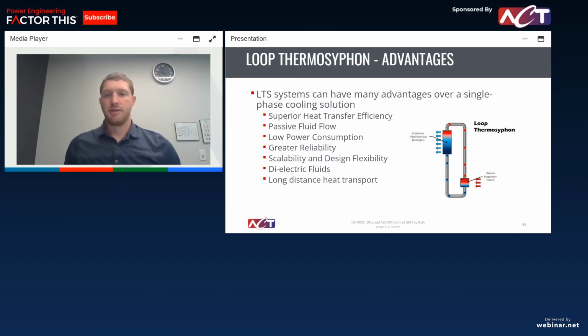So looking at some of the advantages we have over a single phase cooling solution, as we talked about, in general, two phase, you have superior heat transfer efficiency, much higher boiling or latent heat. With no pump, you're going to have passive fluid flow. So gravity is doing all the work. That's going to be much lower power consumption because you don't have a pump in there, and then greater reliability. You don't have to maintain your pump. You don't have to service your pump. That can be very useful, especially in applications where your thermal management solution is not accessible, or you're in a situation where you don't have reliable power.